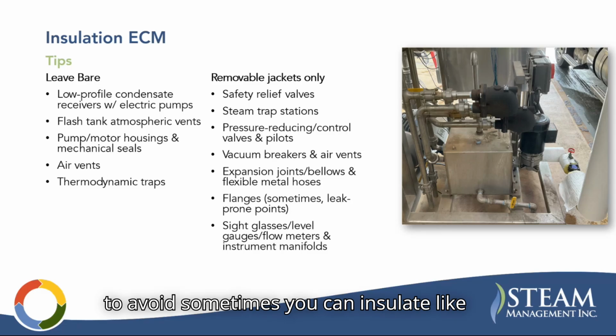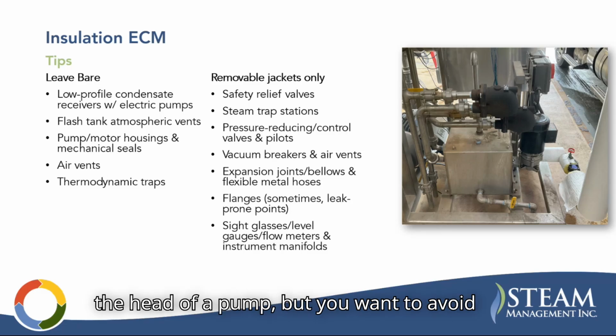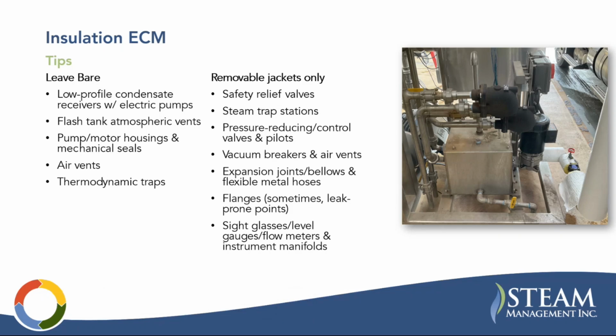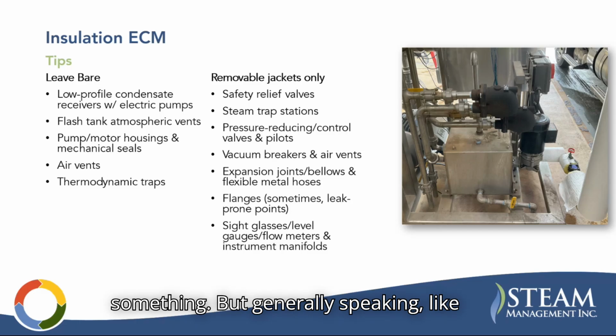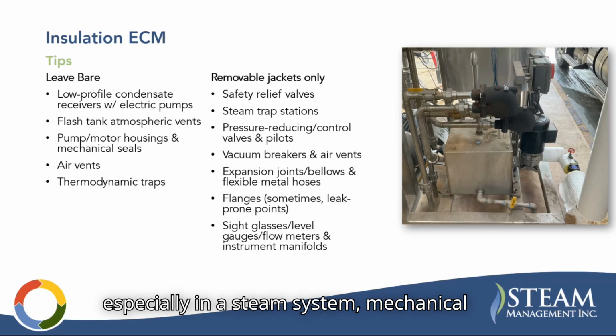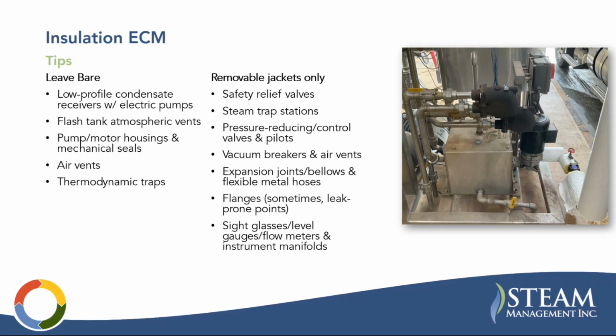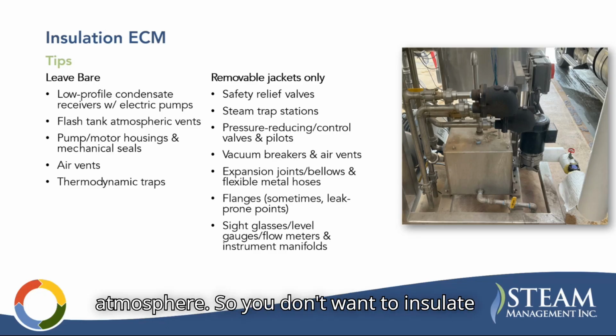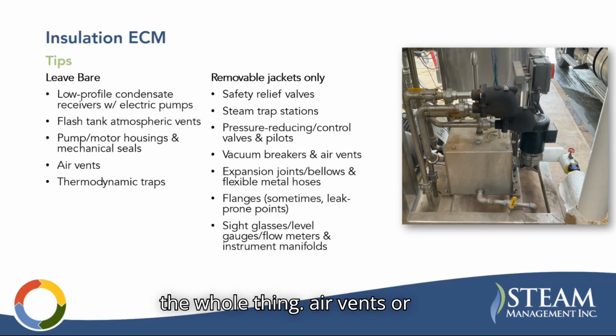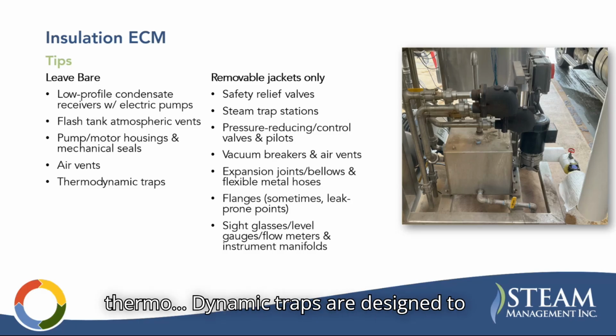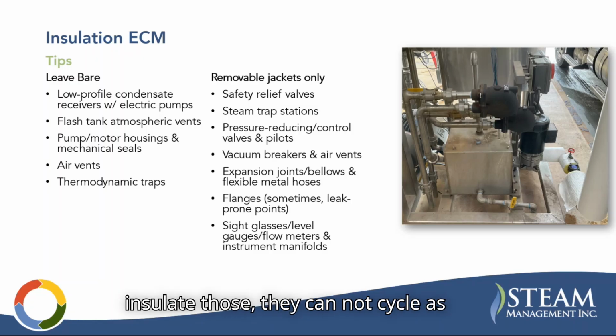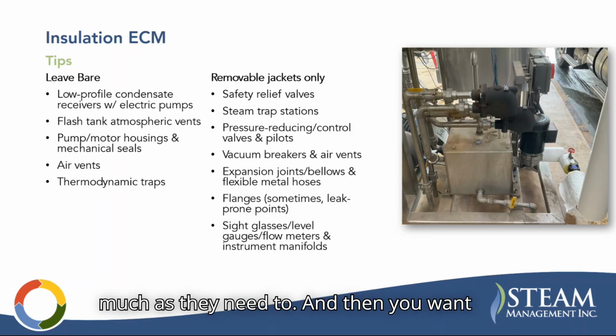Sometimes you can insulate the head of a pump, but you want to avoid insulating motor housings and mechanical seals, unless it's for freeze protection or something. But generally speaking, especially in a steam system, mechanical seals can get overheated, and they need to reject that heat to atmosphere. So you don't want to insulate the whole thing. Air vents or anything that needs to breathe. Thermodynamic traps. Often you'll insulate a lot of your traps, but thermodynamic traps are designed to cool off through the cap. And if you insulate those, they may not cycle as much as they need to.